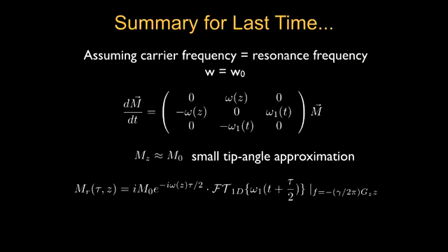The numerical solution is only one way. For a given RF pulse and waveform, you can calculate the slice profile, but you can also go backward. Meaning, for a given slice profile, sometimes people are interested in designing an RF pulse that creates a slice profile similar to the design criteria. With a numerical approach that's not possible, whereas with an analytical solution you can do that. So this brings up many possibilities to design RF pulses for specific applications.